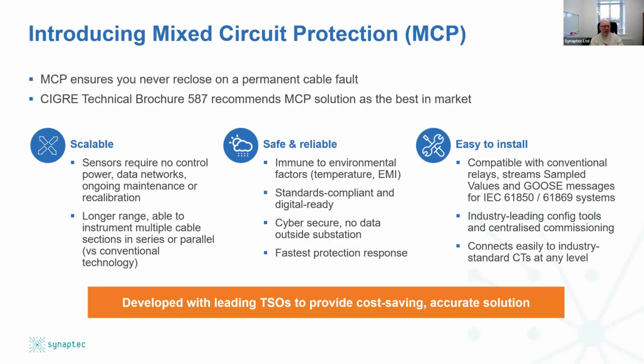Now, our technology is very good for doing this because, as Neil said, you can reach out from the substation over long distances. We recently deployed a system which goes up to and even fractionally beyond our maximum quoted range of 60 kilometers, so that you can install sensors and create protected sections far away from the substation, but monitor them centrally. So you've got this idea of reach and distance, a lot of scalability and range that's possible. It's very safe and easy to install, as Neil's already covered, because it's standards compliant.